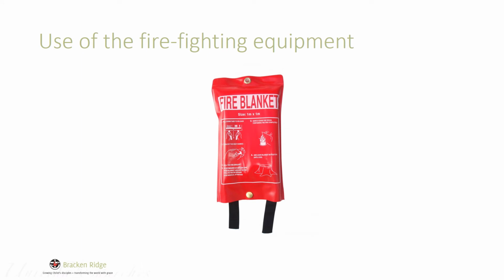Fire blankets are used to put out fires that cannot be extinguished with water alone, and to save people whose clothing may be on fire. Fire blankets work on fires which are being fueled by ordinary combustibles such as wood or paper, by flammable liquids like oil or gas, and by combustible metals including magnesium and titanium.